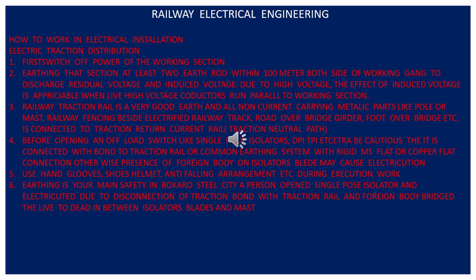Within 2 meters of overhead equipment, if you want to work, then you need permission of an authorized agency like traction power control, or in the station, the station master on the unimportant lines. So first you have to take a permit to work. Then before giving this permission, they will switch off that section. Switch off the section maybe with a load switch which is remotely controlled, but sometimes we need isolation with a single pole isolator, or a substitution double pole isolator, triple pole isolator.